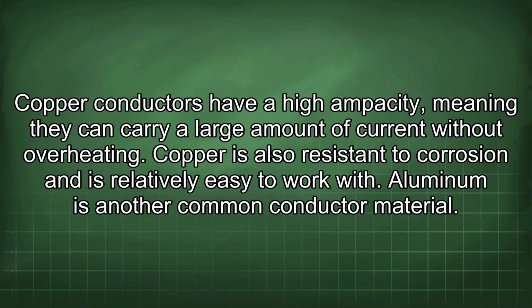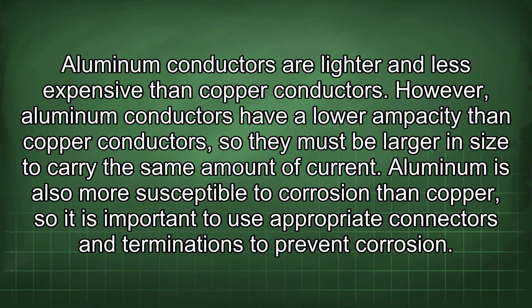Aluminum is another common conductor material. Aluminum conductors are lighter and less expensive than copper conductors. However, aluminum conductors have a lower ampacity than copper conductors, so they must be larger in size to carry the same amount of current. Aluminum is also more susceptible to corrosion than copper, so it is important to use appropriate connectors and terminations to prevent corrosion.